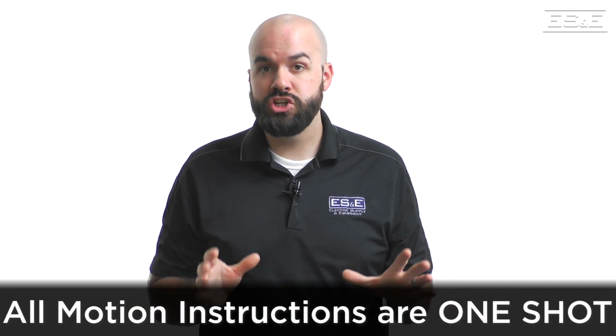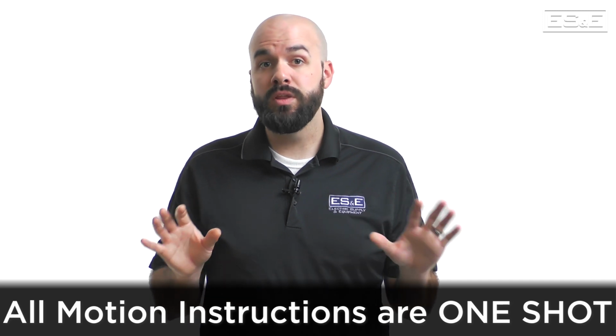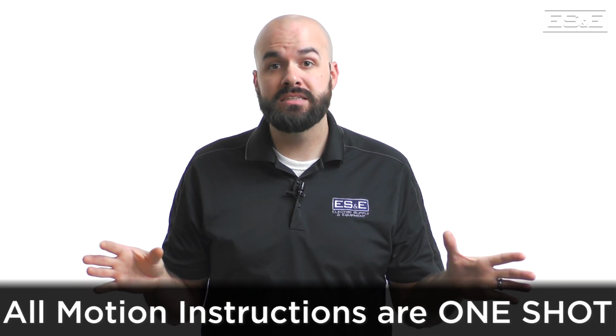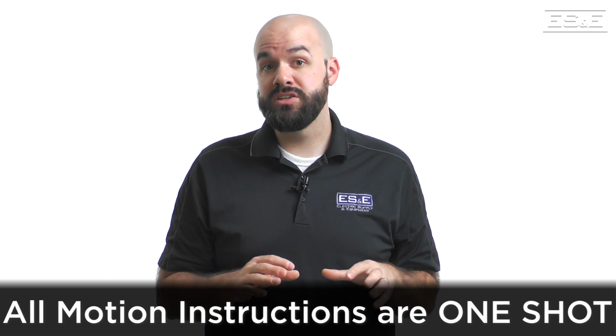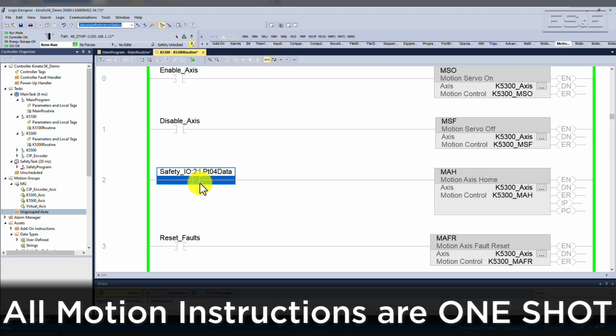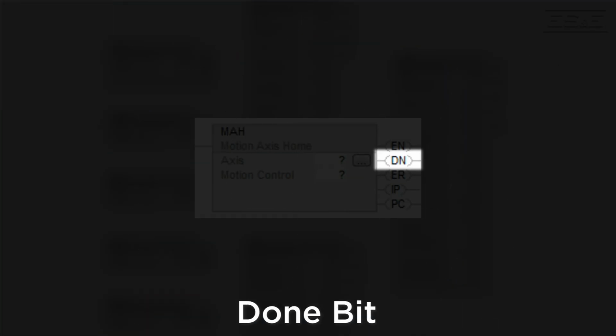Note that all motion instructions are one shot. This means that the only time they perform any kind of task is when the enable bit transitions from false to true. In other words, turning an instruction off will not affect the target axis in any way. The done bit turns on when the instruction has executed successfully with no errors. The done bit will only change states if the instruction is disabled and then is enabled. So, when the enable bit transitions from false to true.